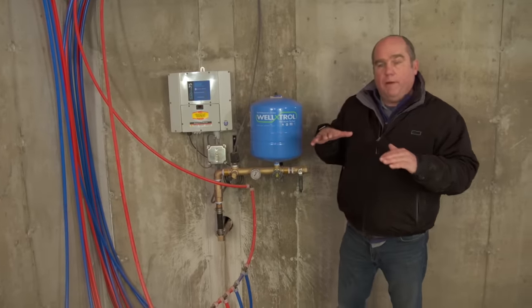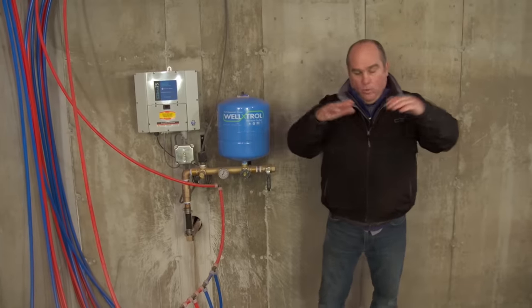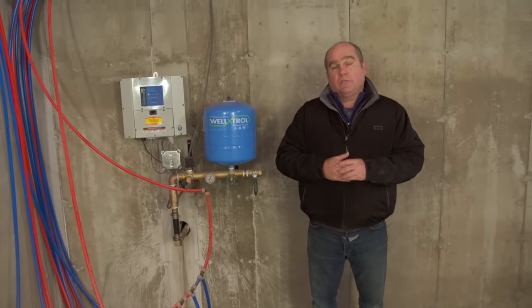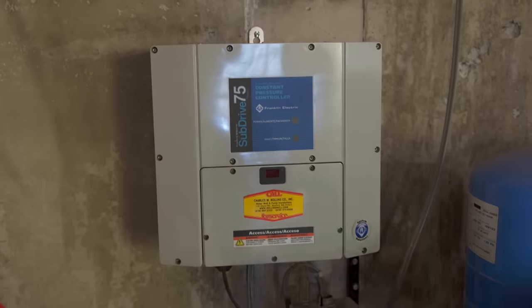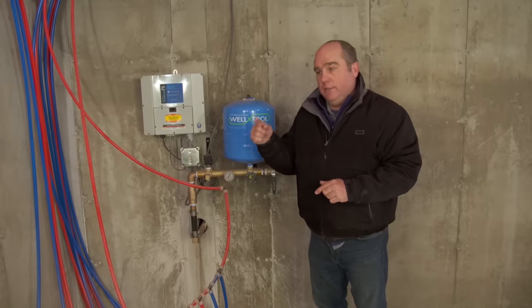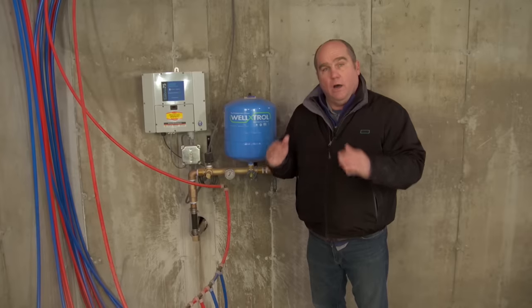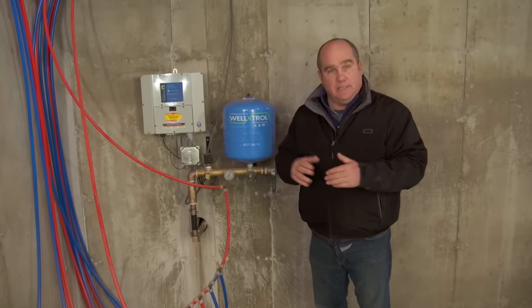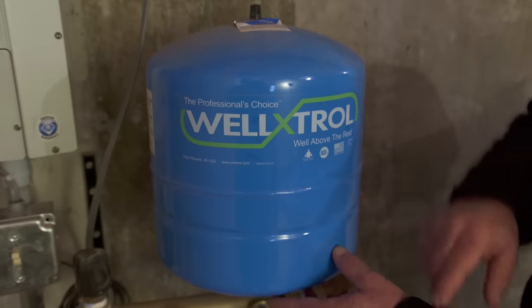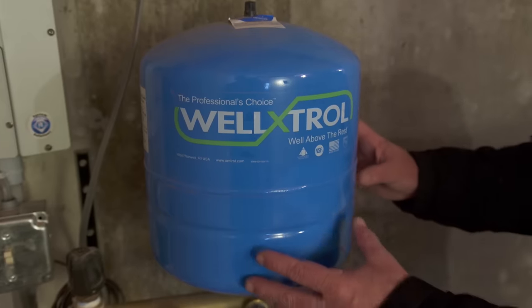In the old days, the well pump would be either on at full blast or off. With that, we needed a big well tank to keep the pump from cycling on and off so much that it would shorten its life. With this new system, it senses the pressure and brings on the pump just the right amount to keep the pressure constant upstairs — a lot like cruise control on your automobile, always keeping the system at 60 pounds pressure. There's also a little diaphragm expansion tank that helps prevent short cycling, but it's much smaller than the big ones we used to need.